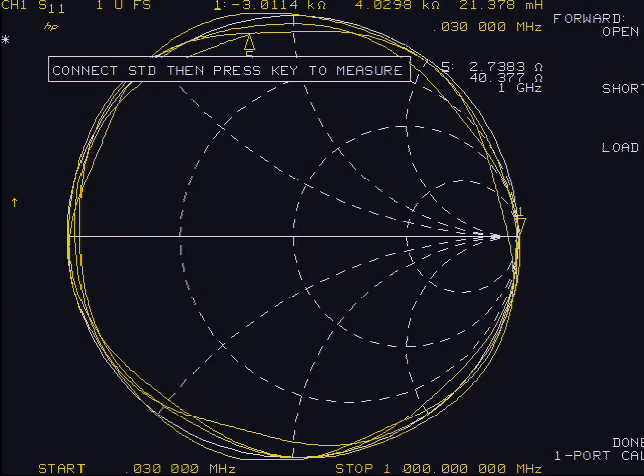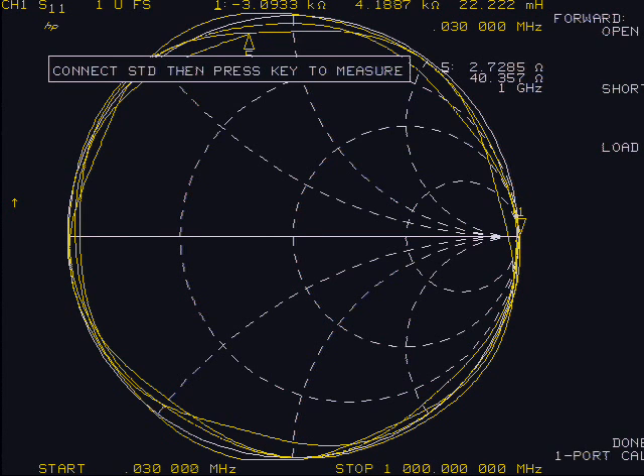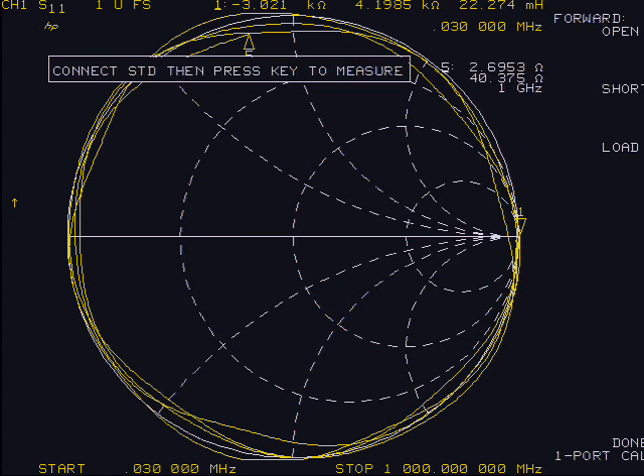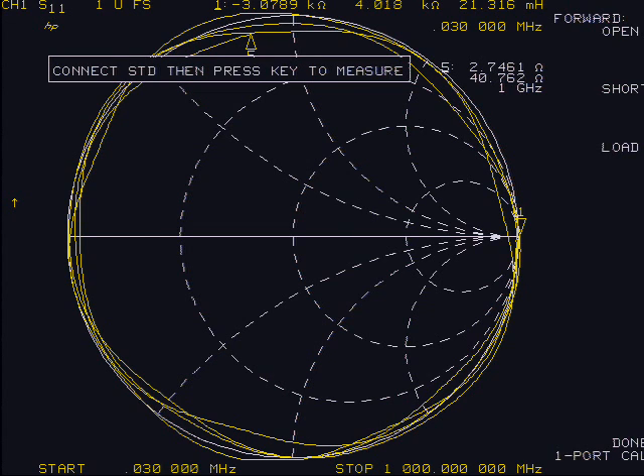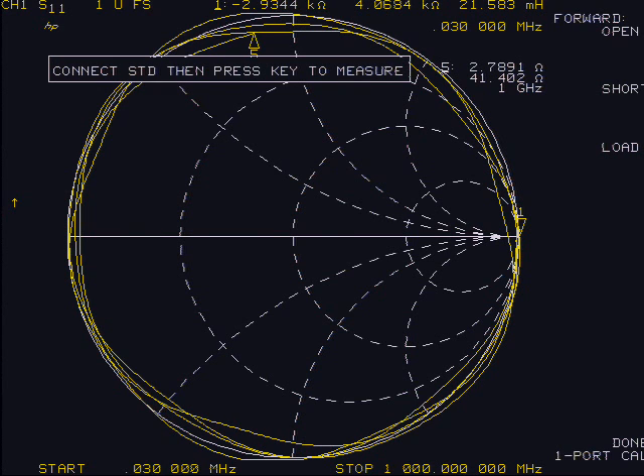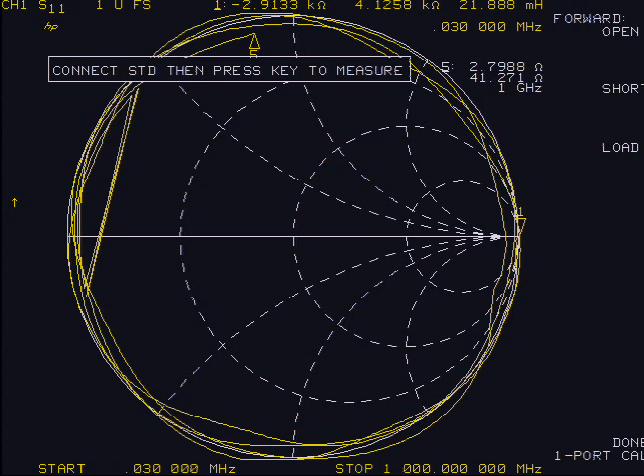Three calibration loads are needed: an open, a short, and load—50 ohms for this analyzer, as indicated by the soft keys. These loads must not just be the right impedance but must be electrically the same length. So although they are physically different lengths, they are electrically the same.